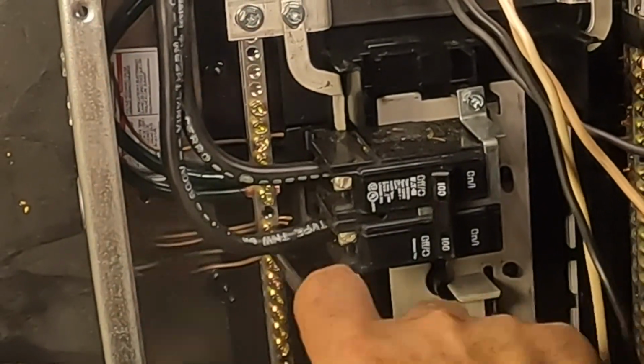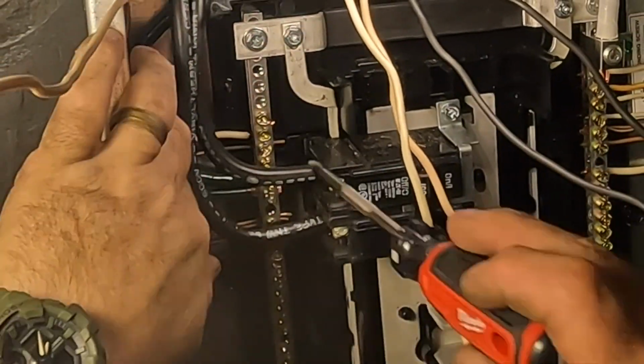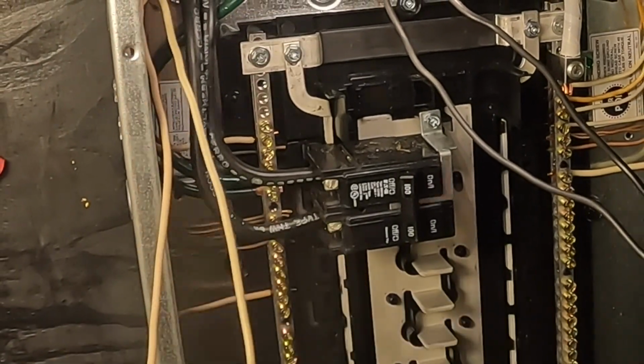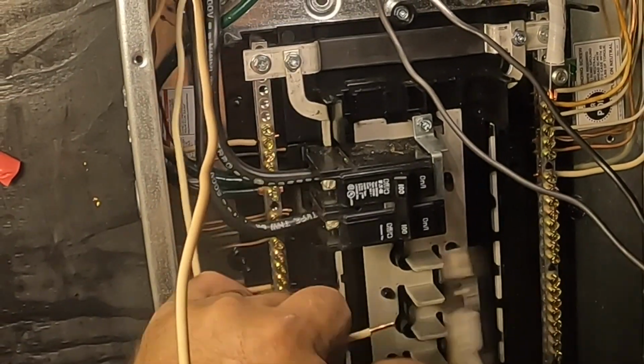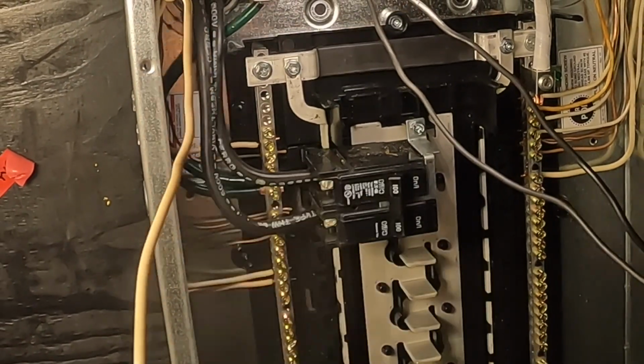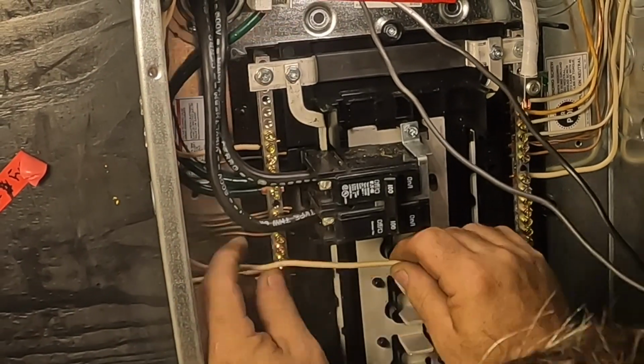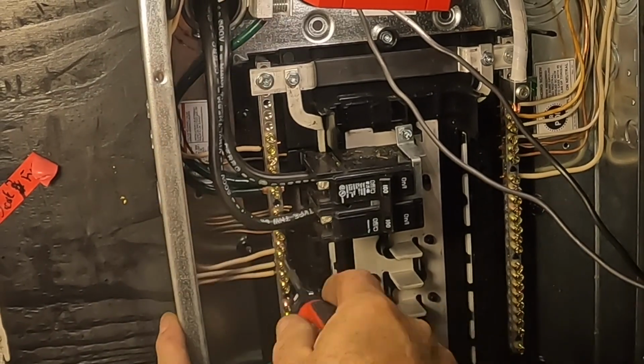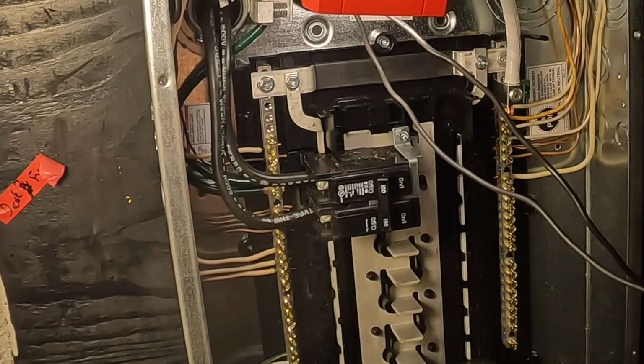Now don't get me wrong, there's actually two things that you do with grounding. Grounding, in case you get hit by lightning, it'll induce a voltage on your circuit conductors. We want to make sure that it has a nice clean path, a low impedance path to earth. And then we have equipment grounding, which is really what we call bonding, and that's going to actually clear a fault in the case of a ground fault situation. So big difference between grounding and bonding.